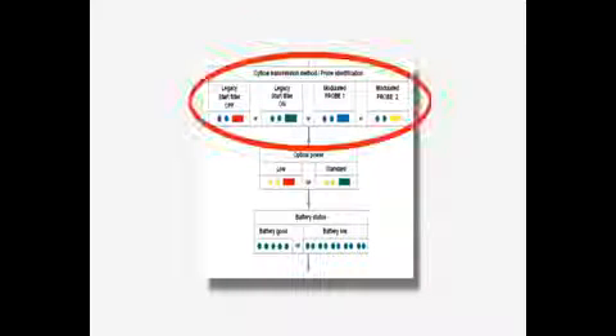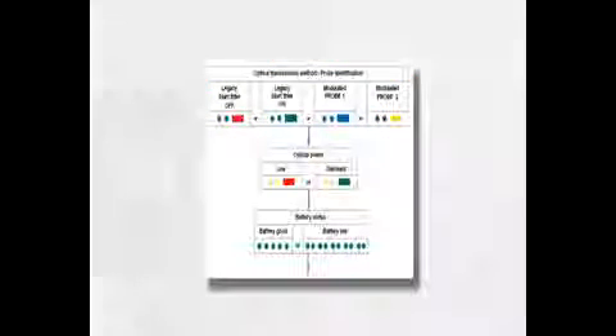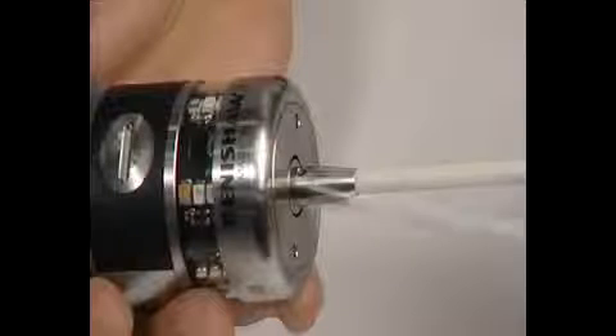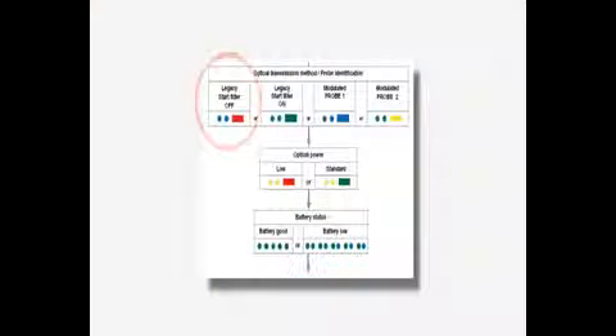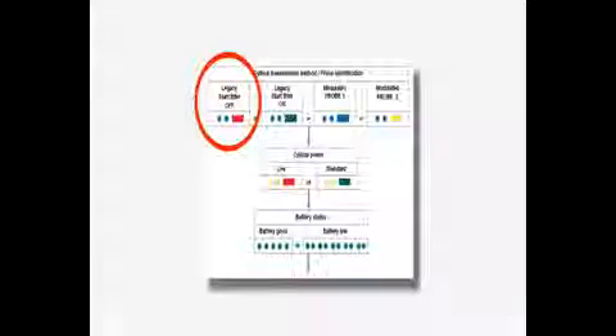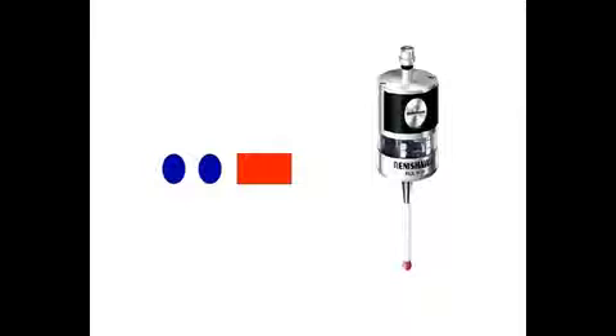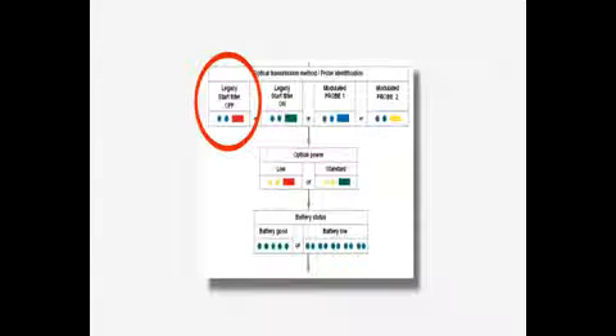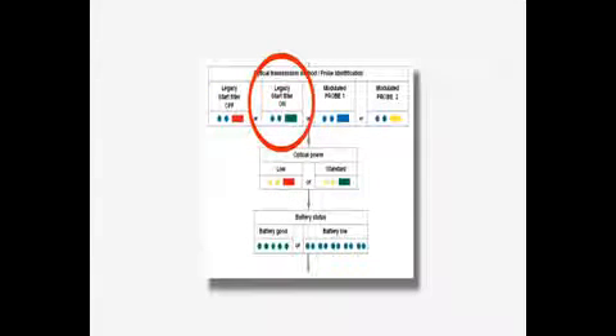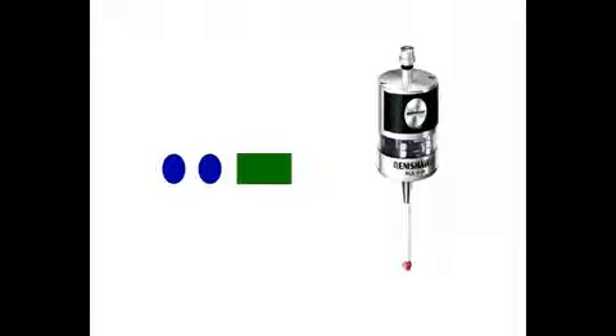The OMP40-2 has multiple transmission modes. These are detailed in the user guide. To change the transmission method, deflect the stylus for 1 second. Blue, blue, red. Legacy transmission, start filter off, for use with OMI and OMM with the MI12 interfaces. Blue, blue, green. Legacy transmission, start filter on. The start filter on option improves the probe's resistance to light interference on startup, for use with OMI, OMM with MI12 interfaces.